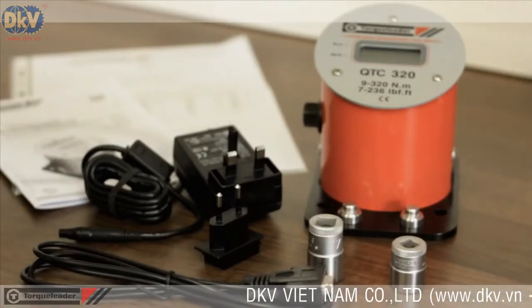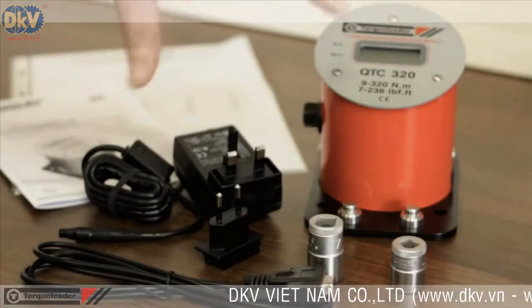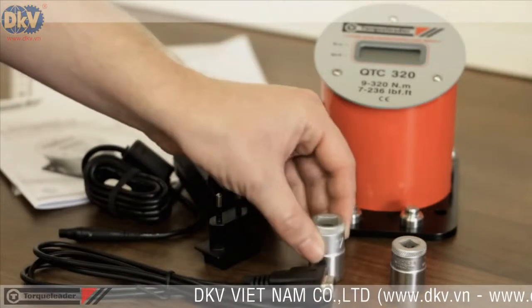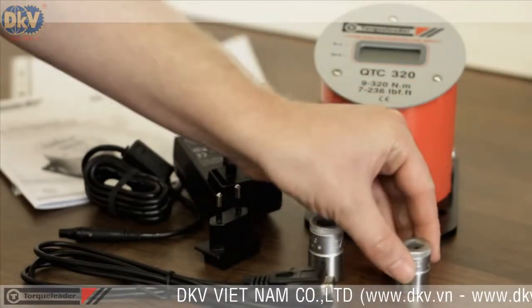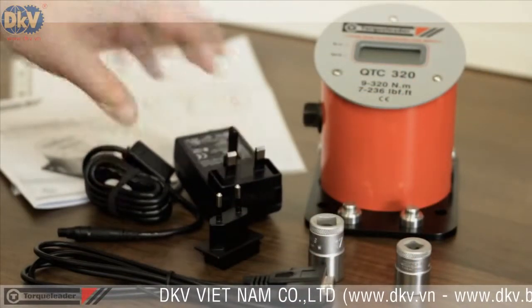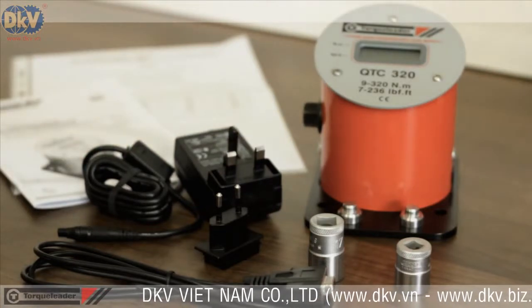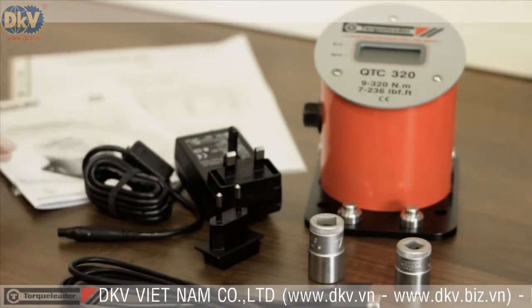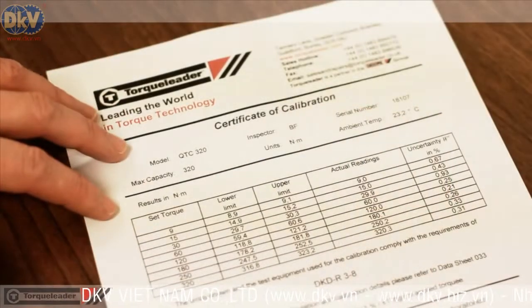Each model in the QTC range is supplied with a full set of accessories: drive adapters to suit different sized torque tools, a mains power lead for use between 110V and 240V, an RS-232 download lead, a full set of instructions, and a certificate of calibration.